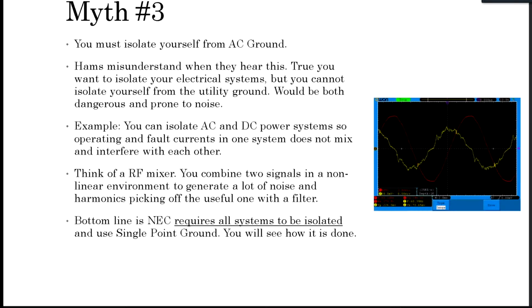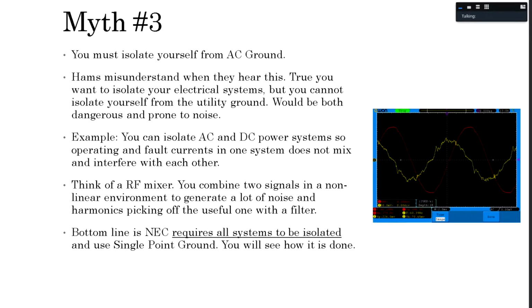Myth 3 is a good one, or more of a misunderstanding. You must isolate yourself from AC ground. Well, like I said, a lot of us misunderstand that. It is true you want to isolate your electrical systems, but you cannot isolate yourself from the utility ground. That would be both dangerous and very prone to noise. Example, you can isolate your AC and DC power systems so operating and fault currents in one system do not mix and interfere with each other.